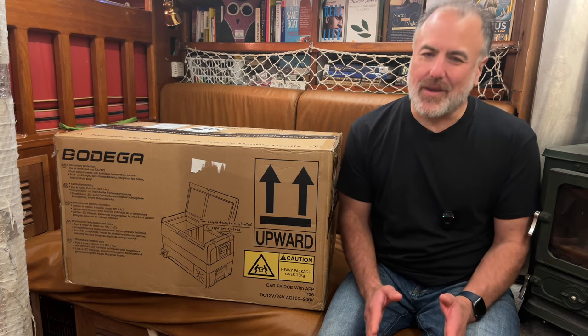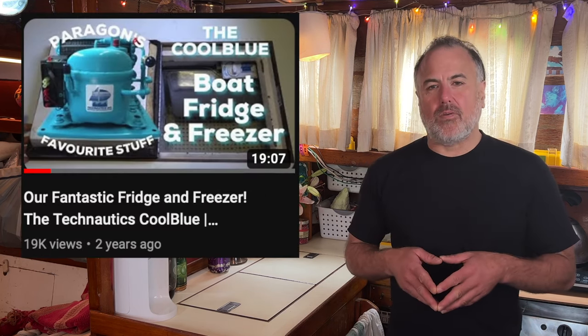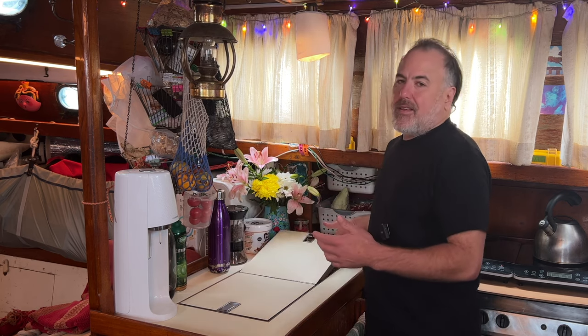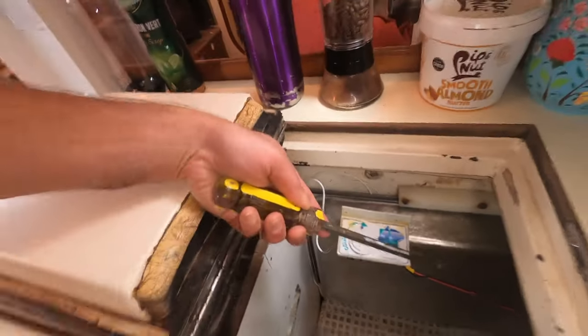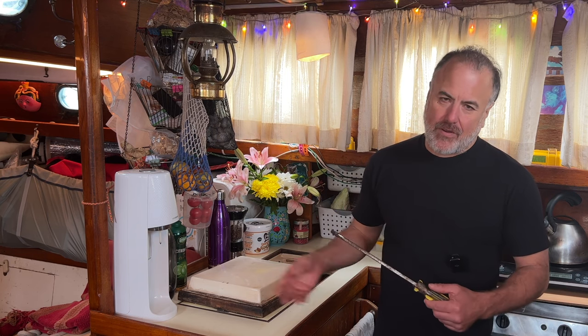For the past 15 years, we have always used a marine refrigeration product called the Cool Blue, made by Technautics. It has always worked really well for us, giving us a massive amount of refrigerated space and a ridiculous amount of frozen goods space — until about three months ago when I wasn't paying attention and I accidentally broke it. The Cool Blue has a big holding plate in the freezer side with refrigerant lines going to it. The holding plate had built up a lot of ice and instead of defrosting it, I was chipping it away with a big screwdriver.